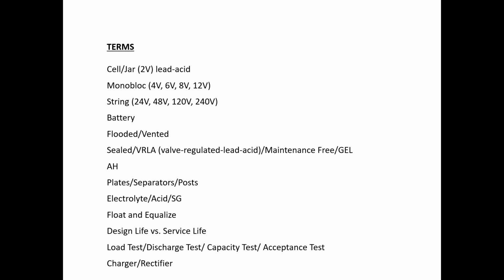Ampere hour is really the size, the capacity of the battery, and that's dependent on the surface area of the positive plate. So typically, the physically larger the battery, the larger the stored energy capacity of the cell is. In the U.S., we usually define ampere hour at an 8-hour rate. So when someone says a battery is an 800 ampere hour battery, it can provide 100 amps constant current for 8 hours to an end voltage of usually 1.75 volts per cell.